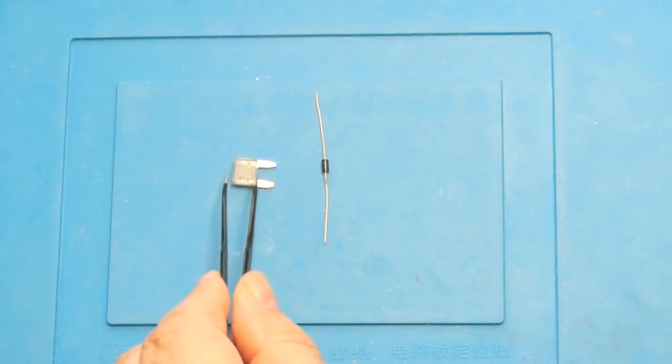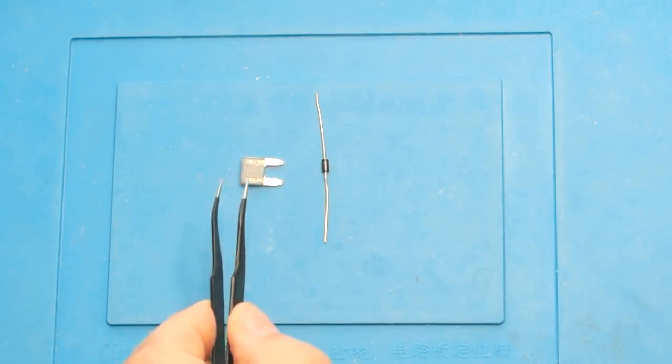It's going to blow the fuse protecting the branch circuit. The problem is once that blows, if you have four or five devices on your circuit, they're all going to go out and you won't know why that fuse is blowing until you check every device on that circuit.